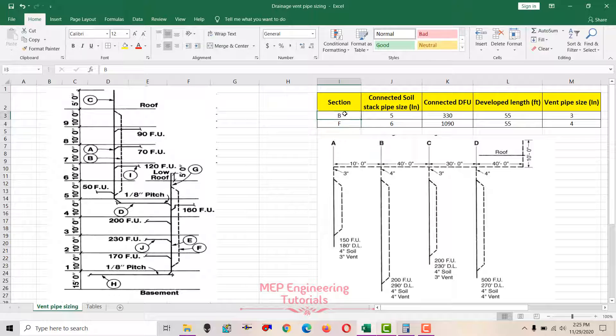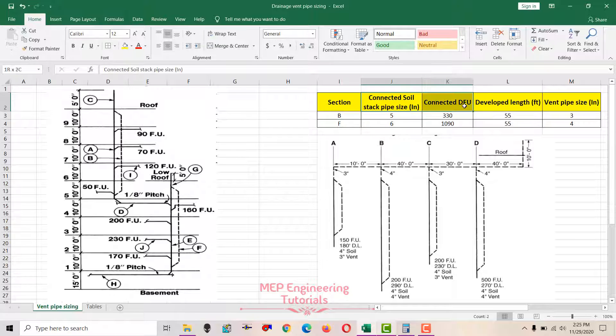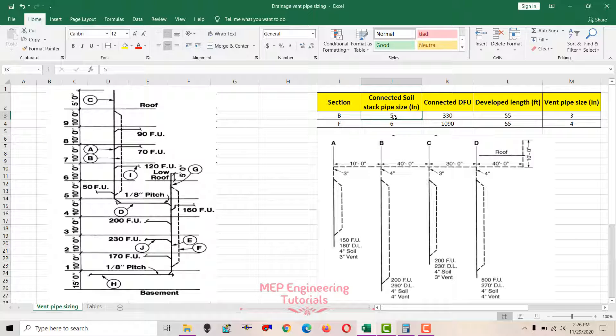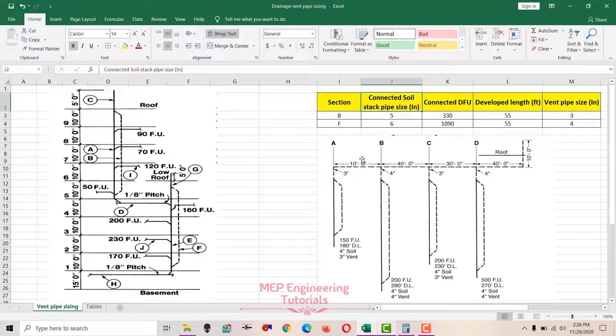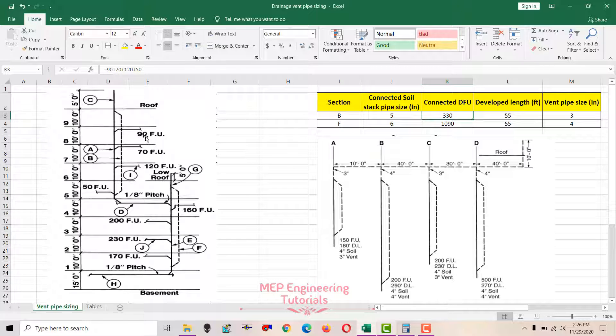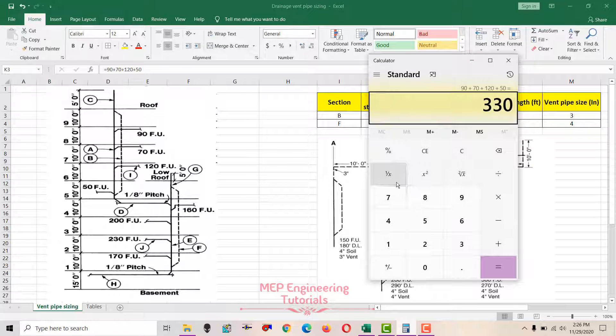For the first example, the vent stack is represented by section B. Three things should be known to get the vent pipe size. First, check the soil stack pipe size — I won't discuss how we got that here; refer to the drainage pipe sizing video for that. The connected drainage fixture units are 90, 70, 120, and 50 across four branches, giving a total of 330 fixture units.